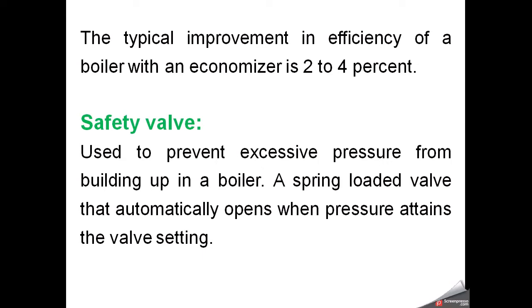An important safety aspect of the boiler system is the safety valve. This is used to prevent excessive pressure buildup. The safety valve is a spring-loaded valve that automatically opens when pressure reaches the set safety point of the steam pressure. When pressure reaches that point, this spring-loaded valve operates and releases the pressure from the boiler.